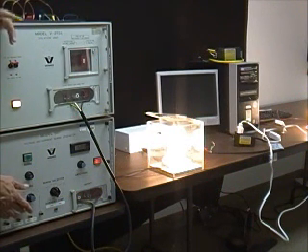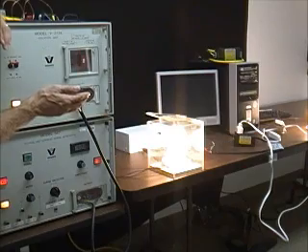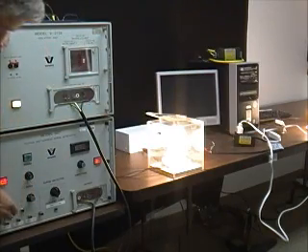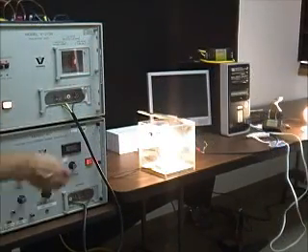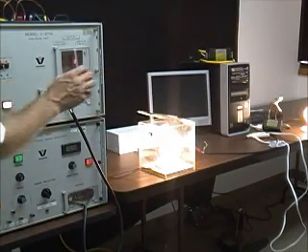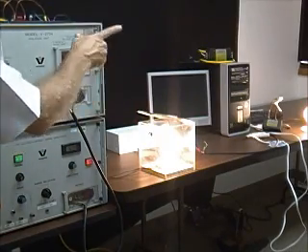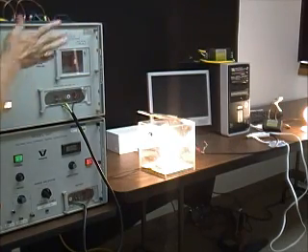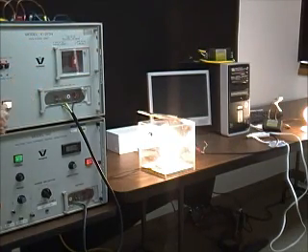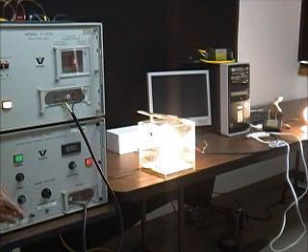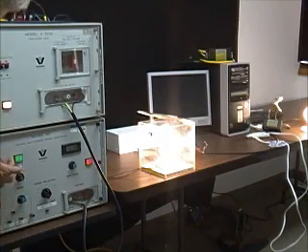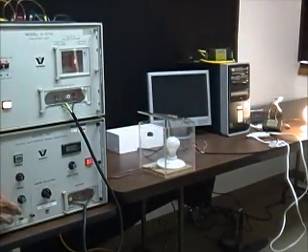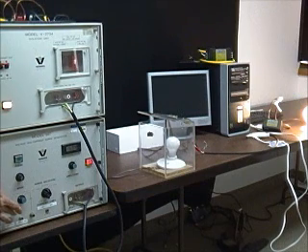Now what we're going to do is we'll add some distance between the first level light bulb and the suppressor. Okay, now what we've done is we've replaced this first level light bulb with a brand new bulb, and we've reversed where the suppressor is. The suppressor is now approximately 12 feet away from the surge. Let's see what kind of benefit can be obtained now that the suppressor is farther downstream. Ready to test. Immediate failure.